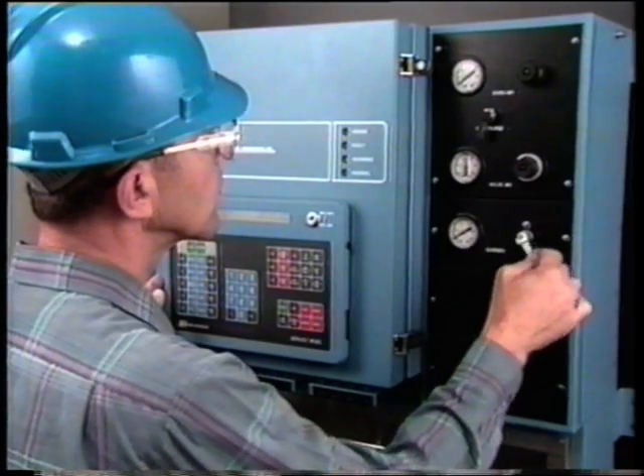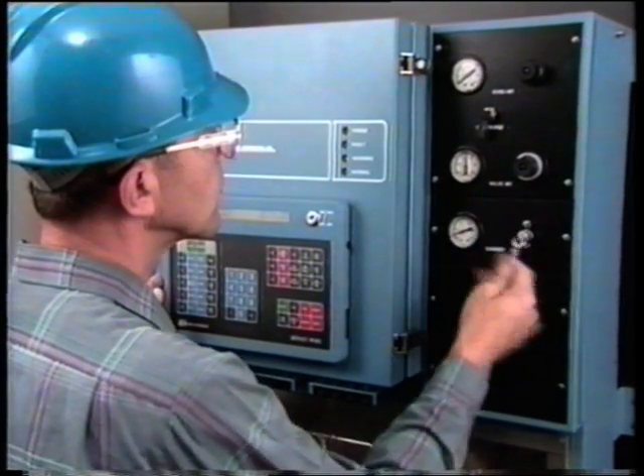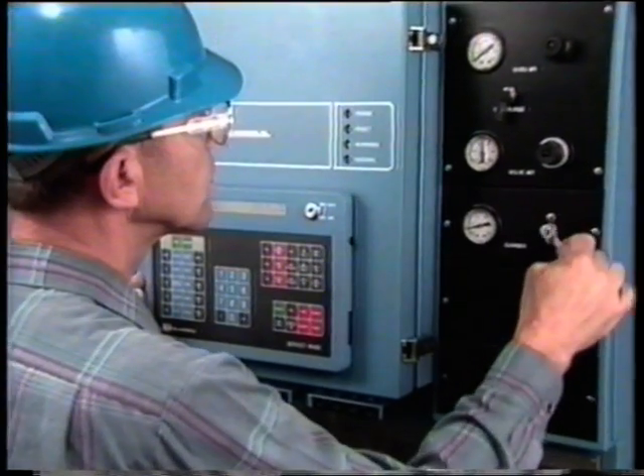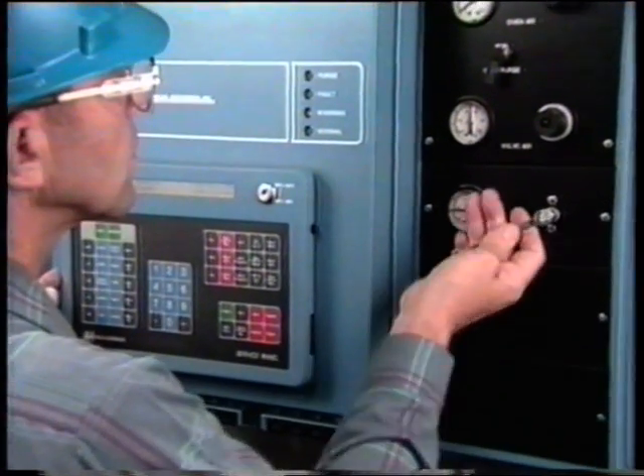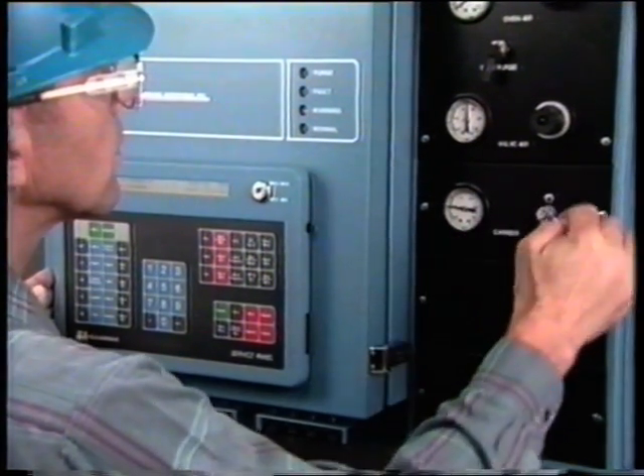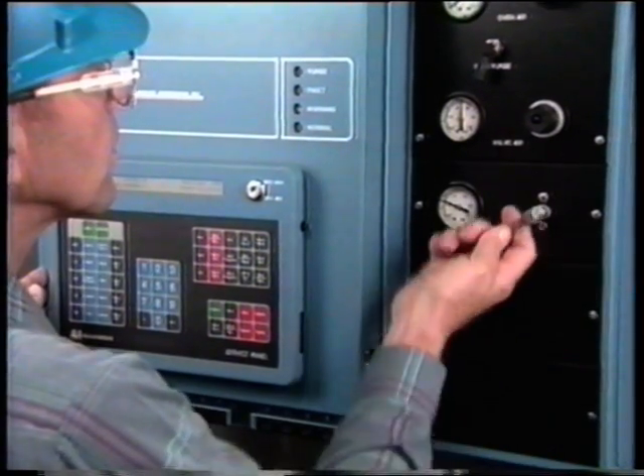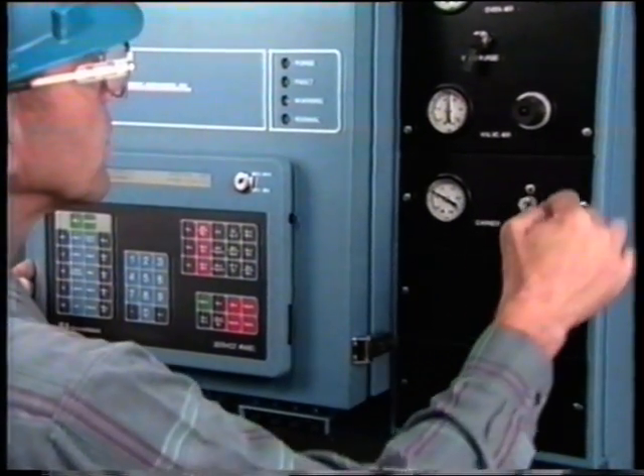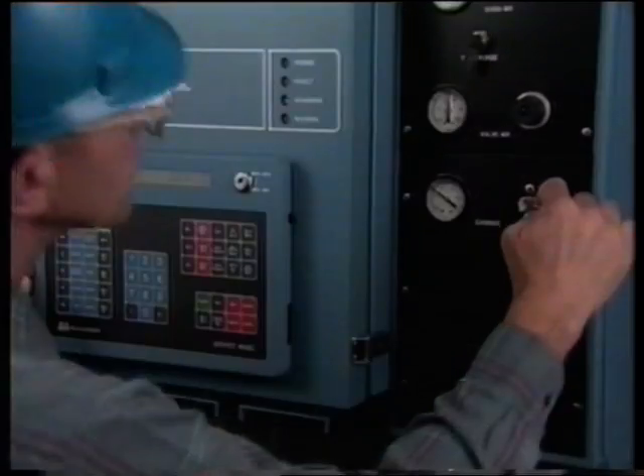After column replacement, the gas chromatograph must be calibrated. Calibration is covered in segment 3 of this tape. In the next segment, you'll learn about gas chromatograph detectors. But for now, review this material in your workbook.